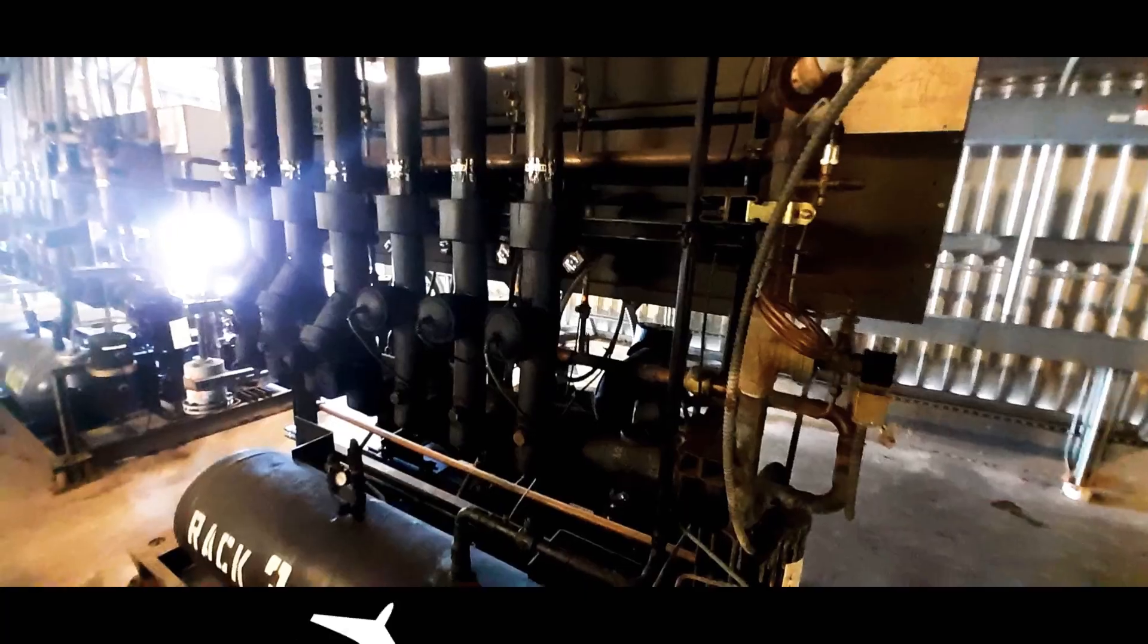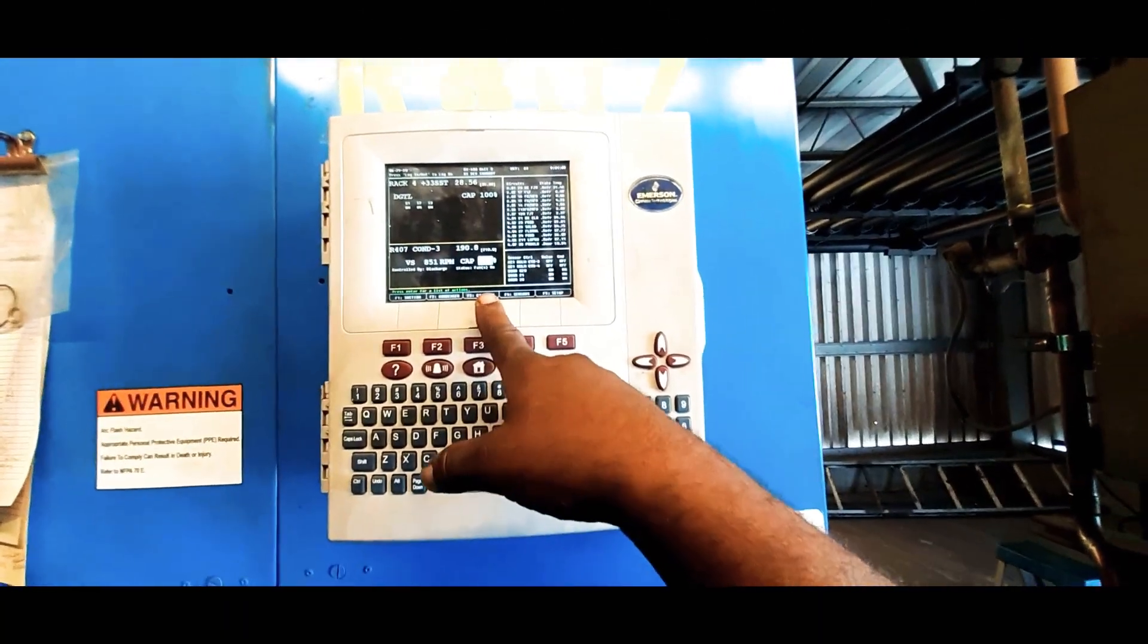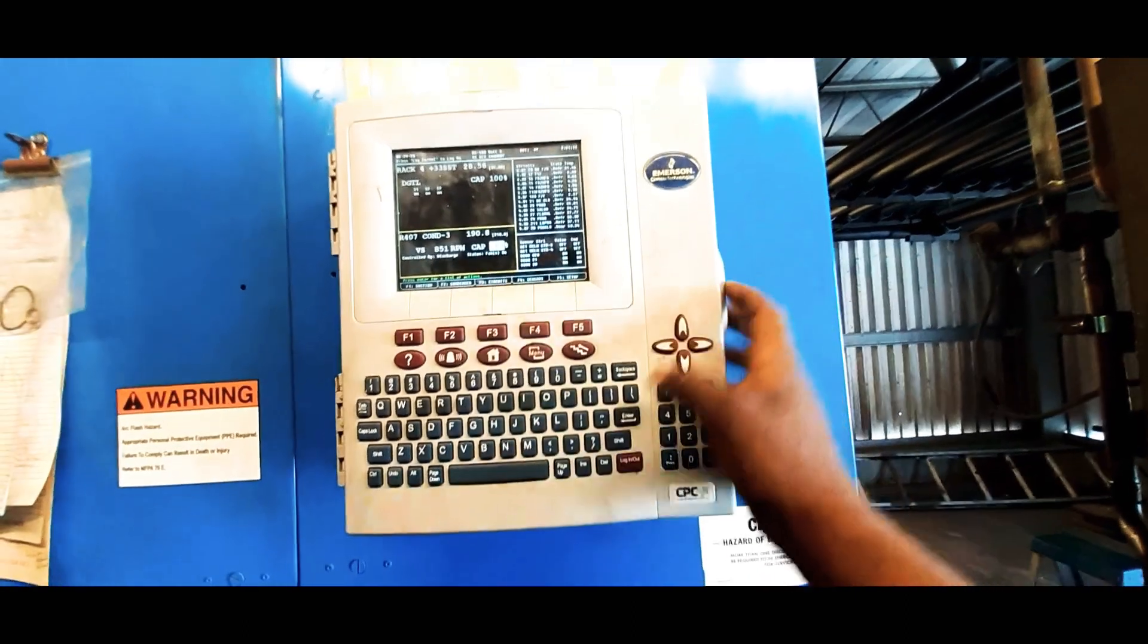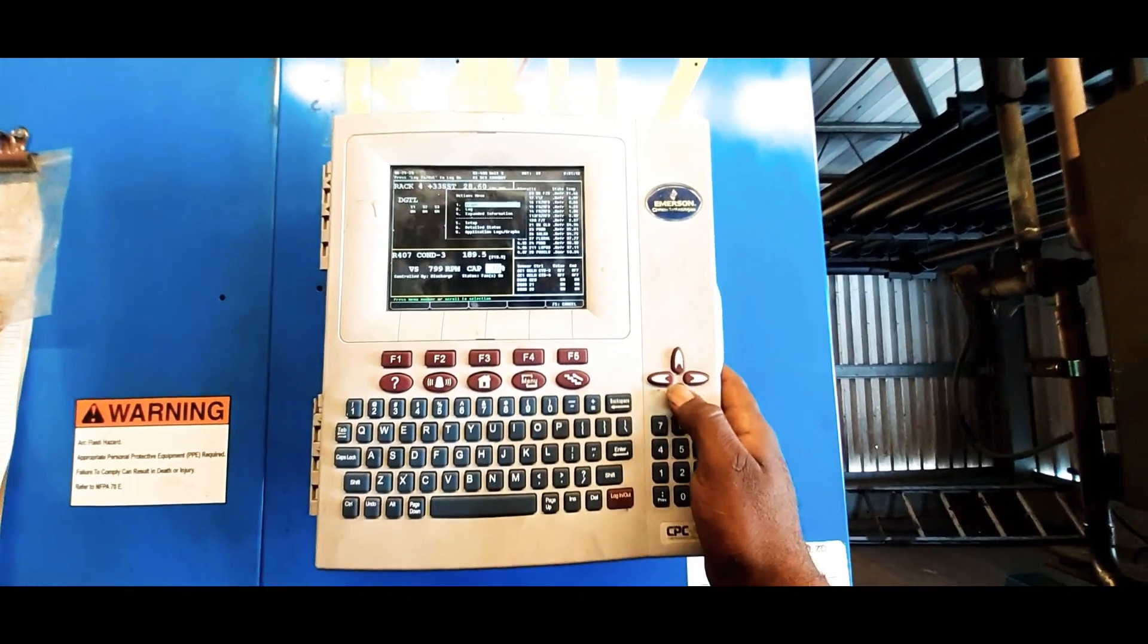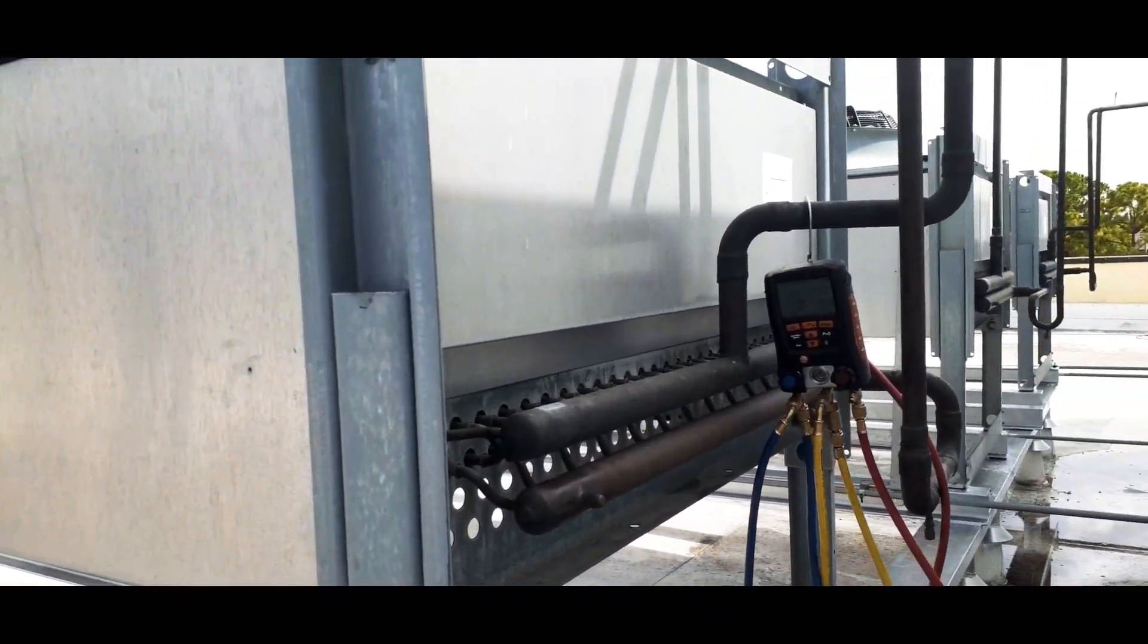Since I just shut off my compressors and valved off my condenser, I'm gonna keep my variable speed fans on high speed. We're going to try to see if we got non-condensables in here.